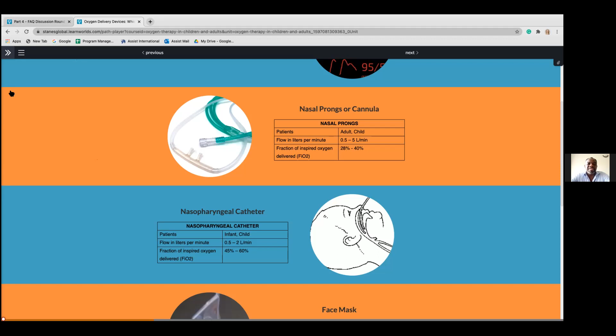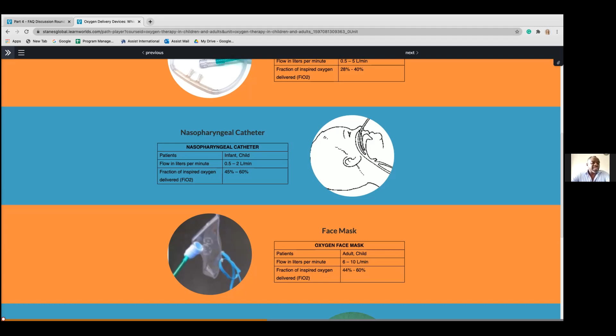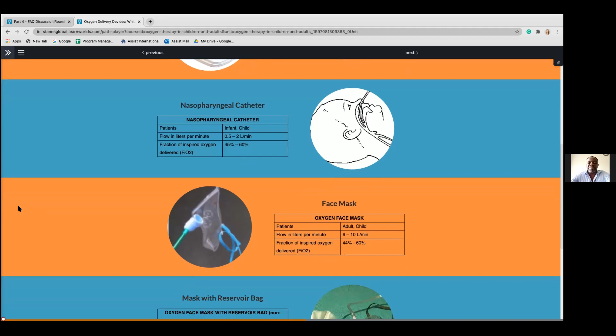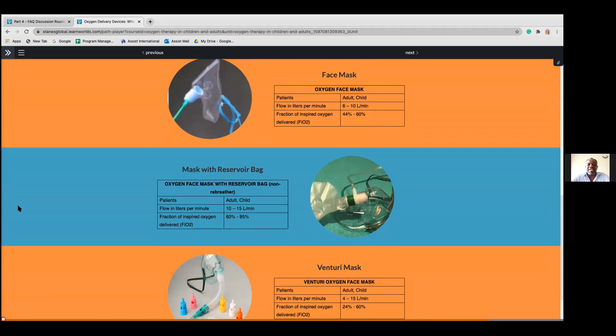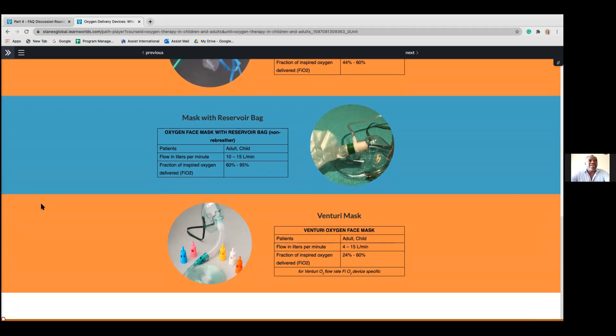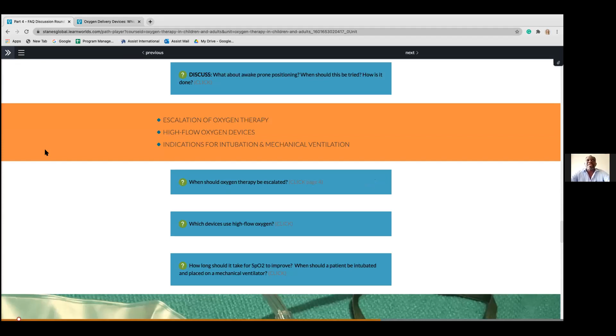To end the talk about the high flow delivery devices, there's also a temperature setting on these devices. To set the temperature, it also depends on what type of patient you are dealing with. We really don't know what the ideal temperature is that you would like to start with. But what is true is that you would not like to give your high flow at a temperature that is lower than the body temperature. Otherwise, you cool down your patient and then they'll be hypothermic. That can also worsen the condition. So the choice of temperature also depends on the patient's condition, and on the temperature that will make your patient a bit more comfortable.